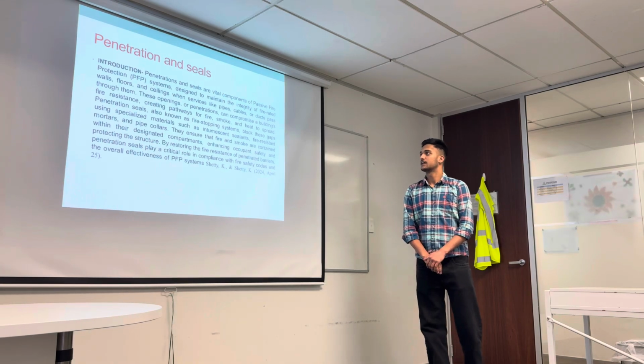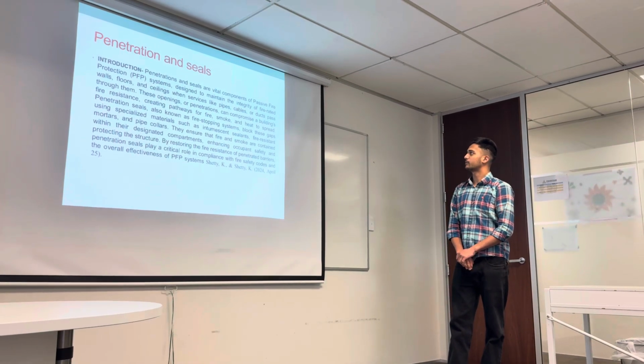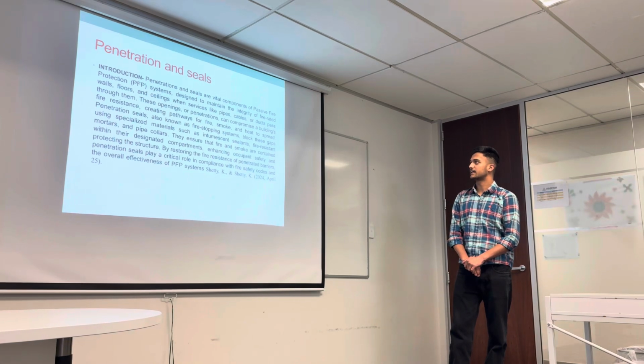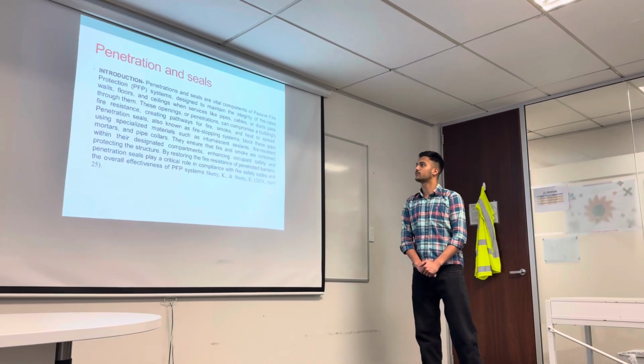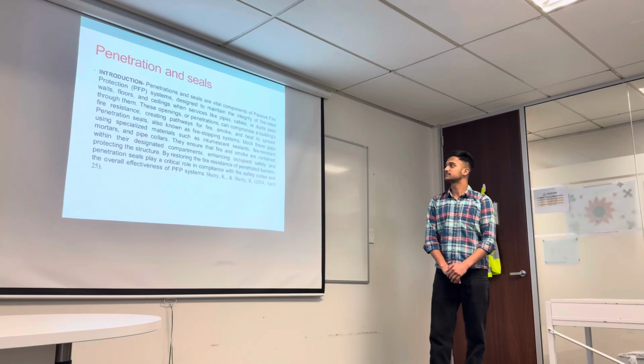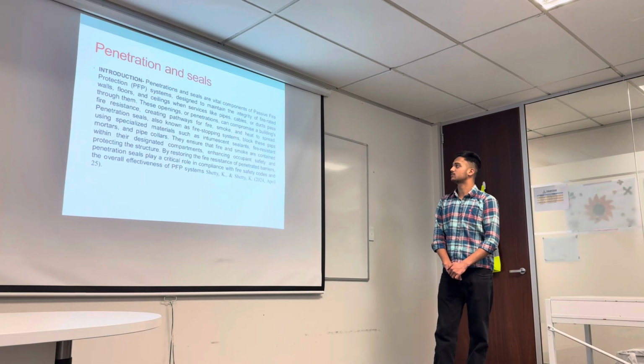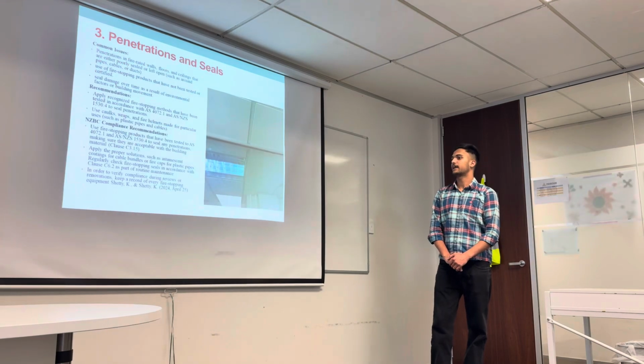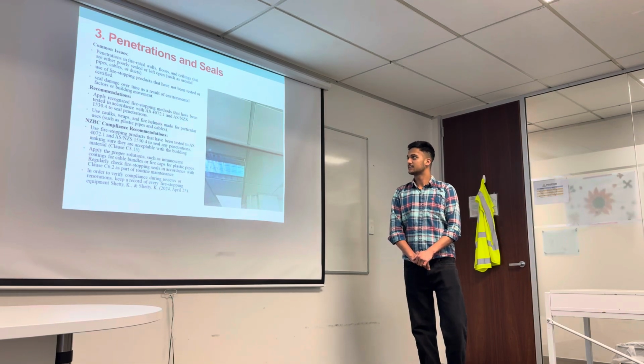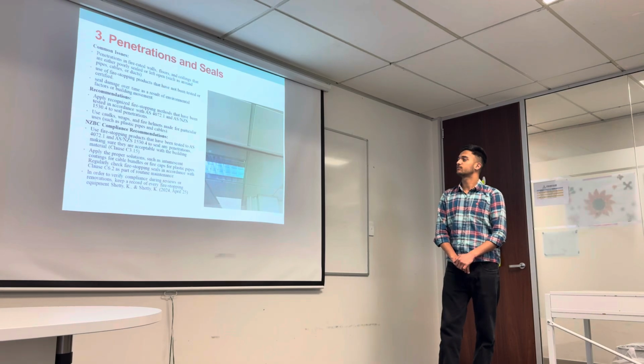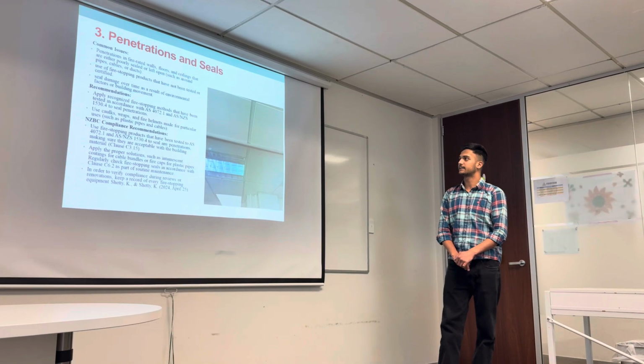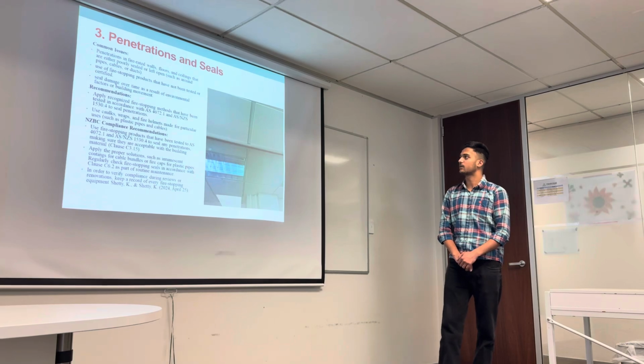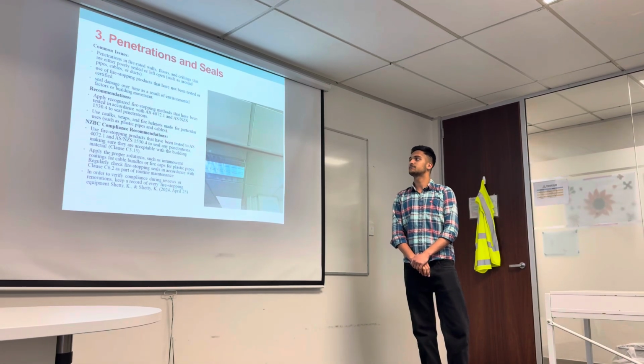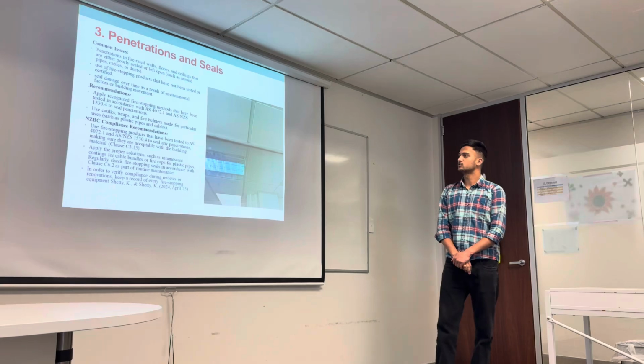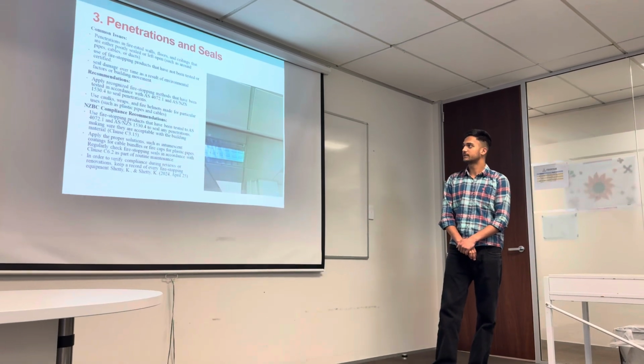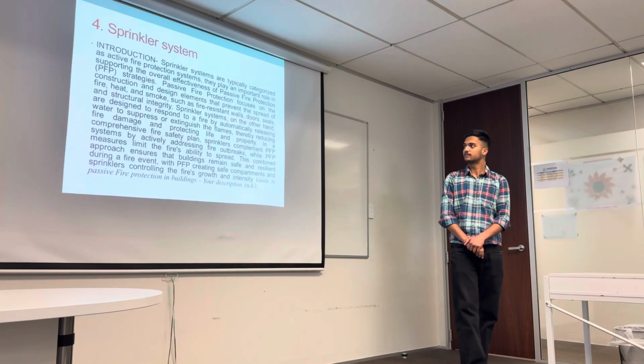Penetrations and seals. Penetrations and seals are vital components of passive fire protection systems designed to maintain the integrity of fire-rated walls, floors and ceilings when services like pipes, cables or ducts pass through them. And the next slide: these are the common issues, like penetrations in fire-rated walls, floors and ceilings that are either poorly sealed or left open, such as around pipes, cables or ducts. Use of fire stopping products that have not been tested or certified.